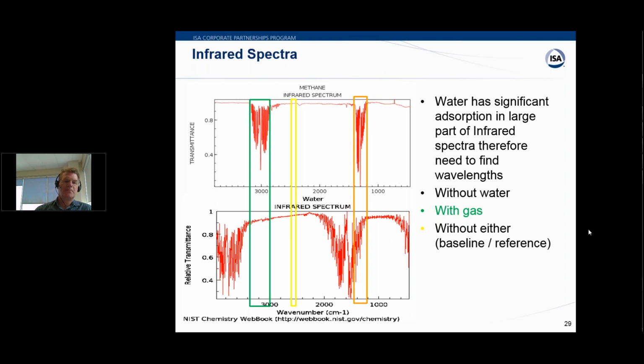And then we would actually calibrate our gas detector to be at about the 3000 point here for methane, because we have a nice big methane response, and it's relatively flat for water there. So that's typically why we do the dual wavelength. Dual wavelength will also help us detect if we have dirty mirrors, these types of things as well. So infrared is quite specific, and that's why it's starting to become more popular.